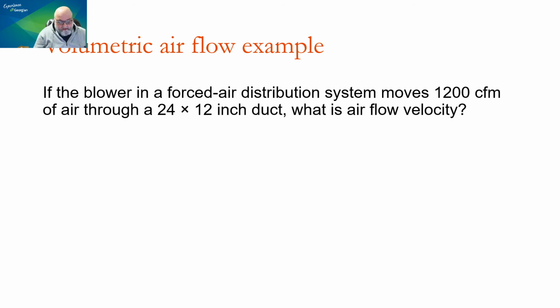Here's an example. If the blower in a forced air distribution system moves 1200 CFM of air through a 24 by 12-inch duct, what is the airflow velocity?